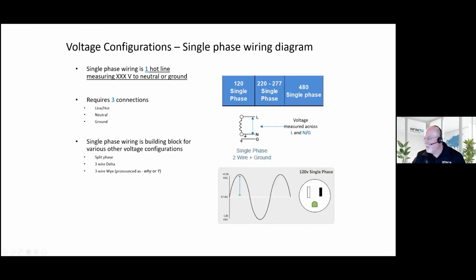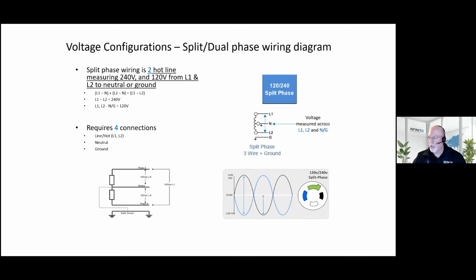I just threw these in for reference material, but it's critical to know, if it's an AC surge protector, the exact voltage configuration of the panel. Now, we talk to a lot of electricians who say they want 240 single phase. And so when I ask them how many hot phases there are, they tell me 2. Because, if you measure line to line or phase to phase, you're going to measure 240. But if you measure from neutral to either leg or line, you're going to measure 120. That's what this means. So they call it 240 single phase, but there's 2 phases.